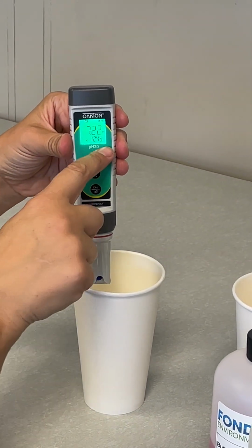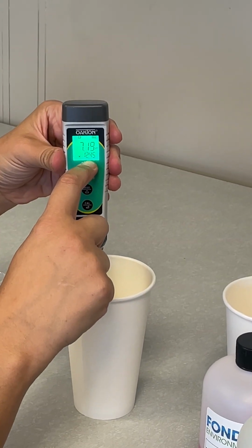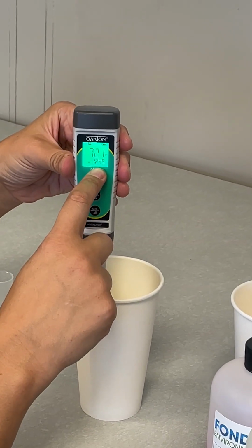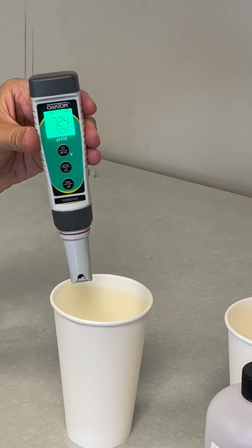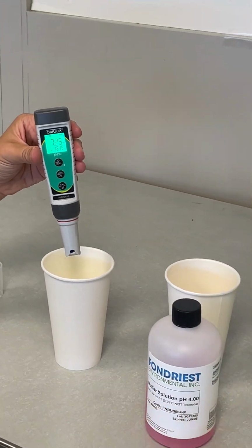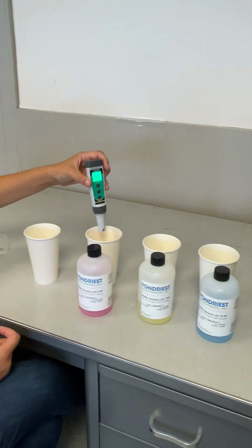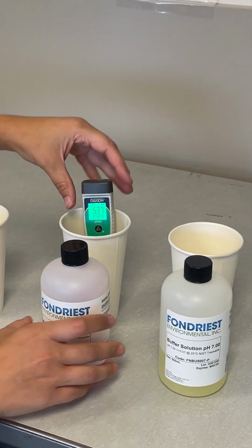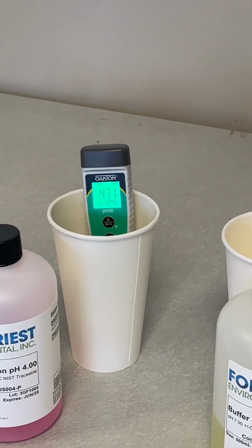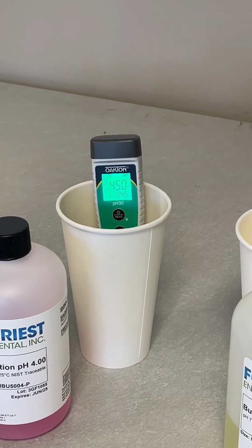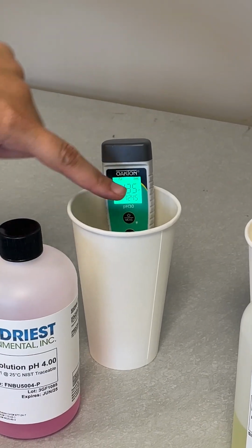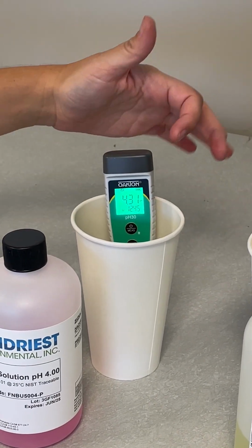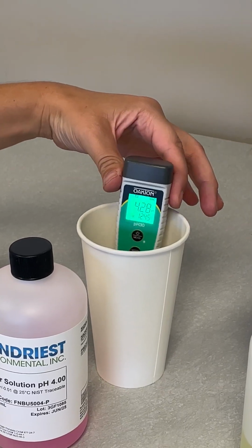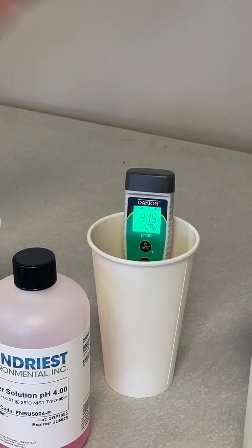And then you're gonna long press calibrate again, and it'll light up. And this time, instead of saying 7 down here, it's just gonna jump around to all these different numbers. Don't worry about that too much. Just pick whether or not you wanna start with the 4 or the 10, it doesn't matter. I'm just gonna start in 4, and once again, you just stick it in the water, and the numbers will even out. Eventually down here, the pH meter will recognize that it's in 4, and it'll say 4.